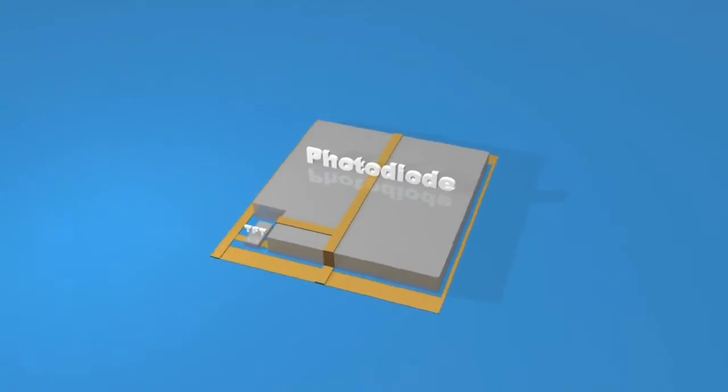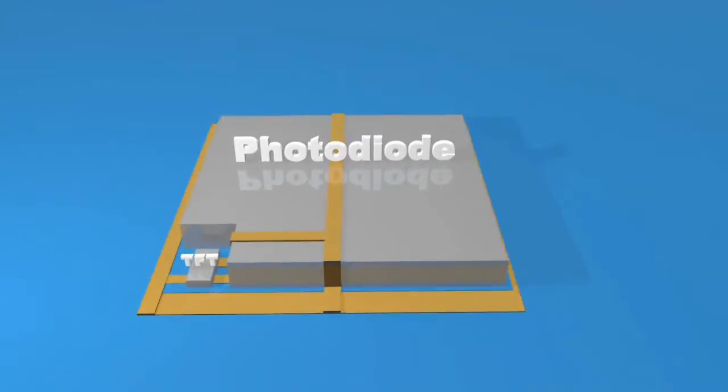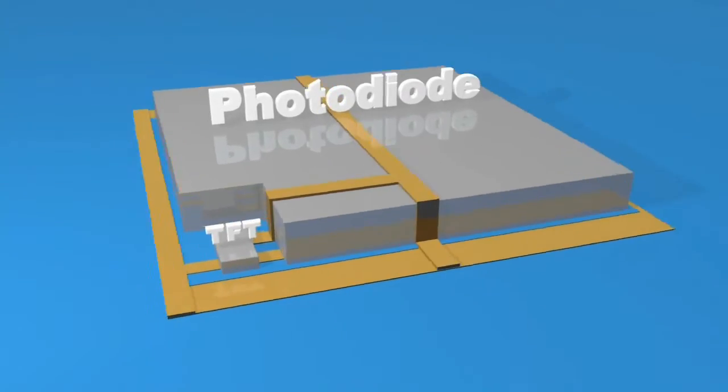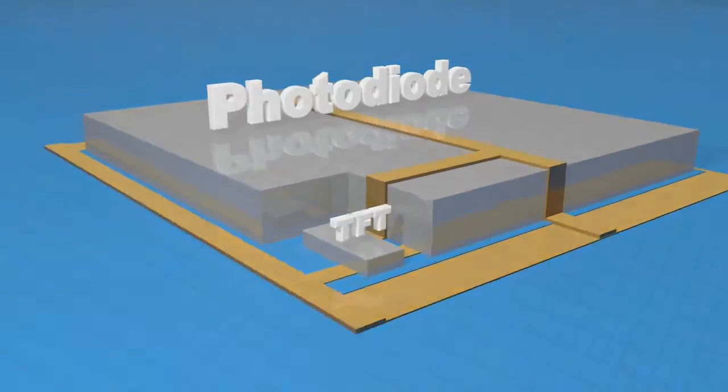Photo-diodes are built in the same layered manner as the TFTs. There is one TFT and photo-diode for each of the up to 7 million pixels on an array. This gives the final image its high resolution.